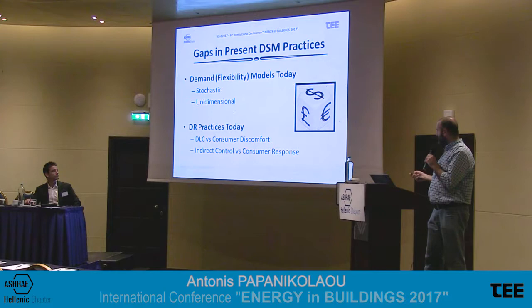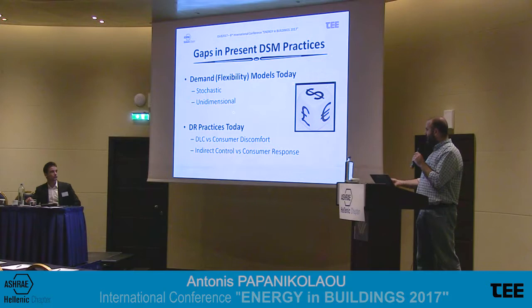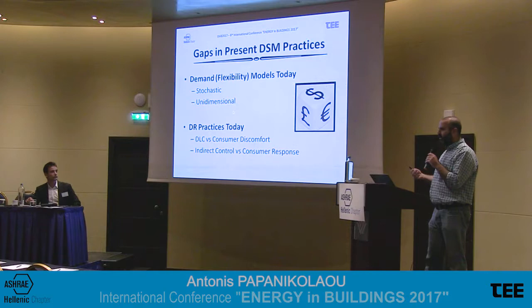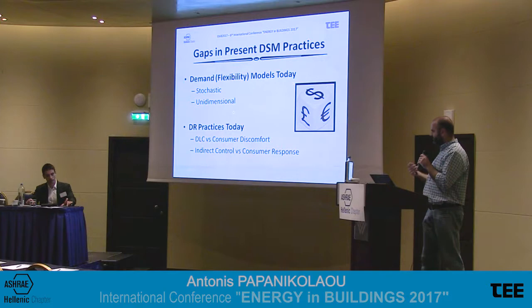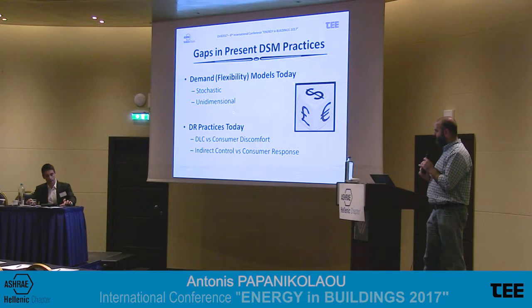The second main technique is indirect control, which basically means that the grid operator will send a signal to the human living or working in the building saying that I need you to change your consumption profile. But whether that happens or not is entirely up to the human, whether they actually take the manual action to change the consumption profile. The experience so far is that the first approach works really well in terms of performance and effectiveness for the grid, but nobody wants to use it. The second one does not work well, but of course everybody wants to have control.